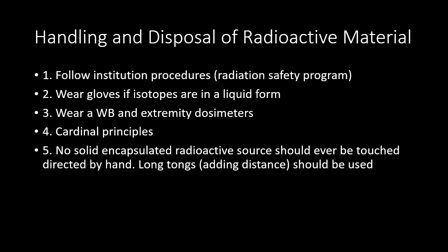Third, wear a whole body and extremity dosimeters, both. Fourth, cardinal principles, always use your time, distance, and shielding, but more importantly, distance and time are very important in this case. And finally, no solid encapsulated radioactive source should ever be touched directly by hand. Long tongs adding distance should be used.